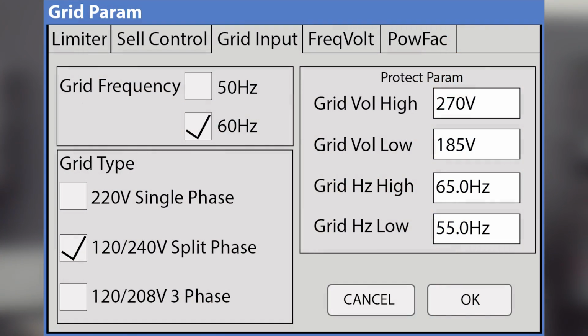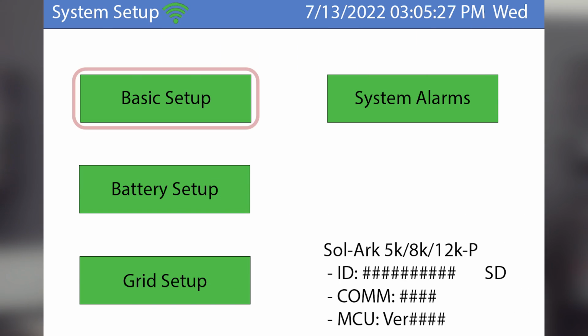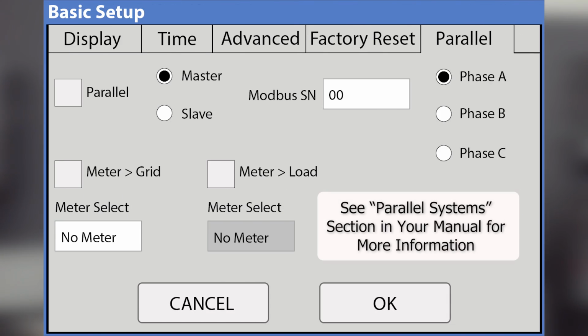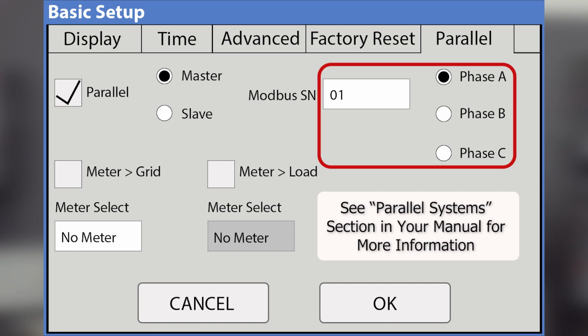So if you're doing 3, you would want to put them all in 120/208 mode, and you would also want to put them into parallel, which I skipped over before. But if you wanted to put them in parallel, you'll go to Basic Setup, and you're going to go over to the Parallel tab, and then you'll select Parallel, and there's going to be one master. Well, actually, it depends. If you're doing 240, there's one master, and then the rest are slave units. With 208, you're going to have, and you have 3 units? 3 of them. So you'll have 3 master units. So there's going to be master 01 with this number right here. These are very important. You can't skip these numbers or it'll make everything go wonky. You need to do 1, 2, 3, not 1, 3, 5 or something. Okay, 1, 2, 3. So master number 1 will be for phase A. Master number 2 will be phase B, and master number 3 will be phase C.